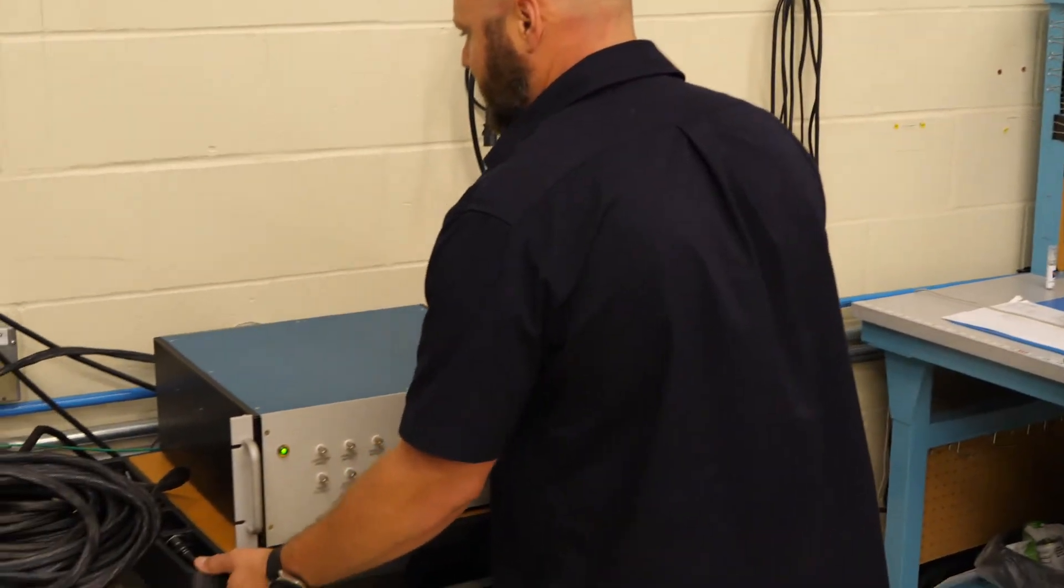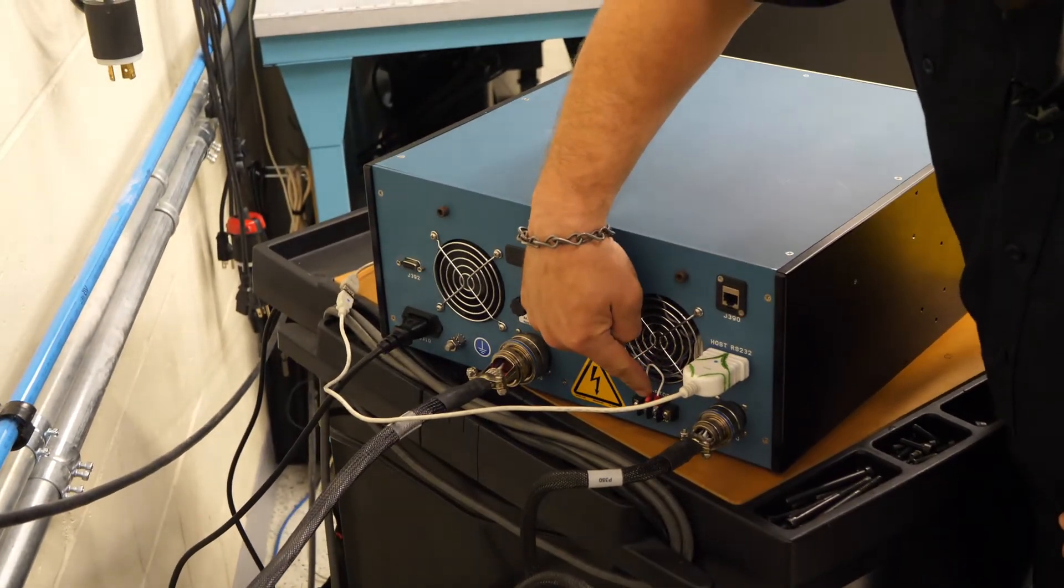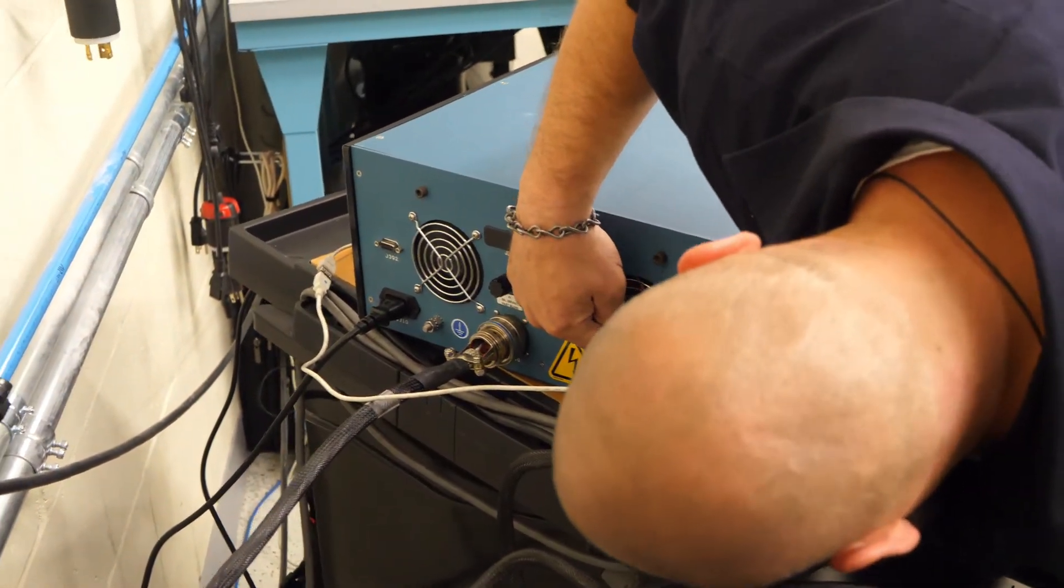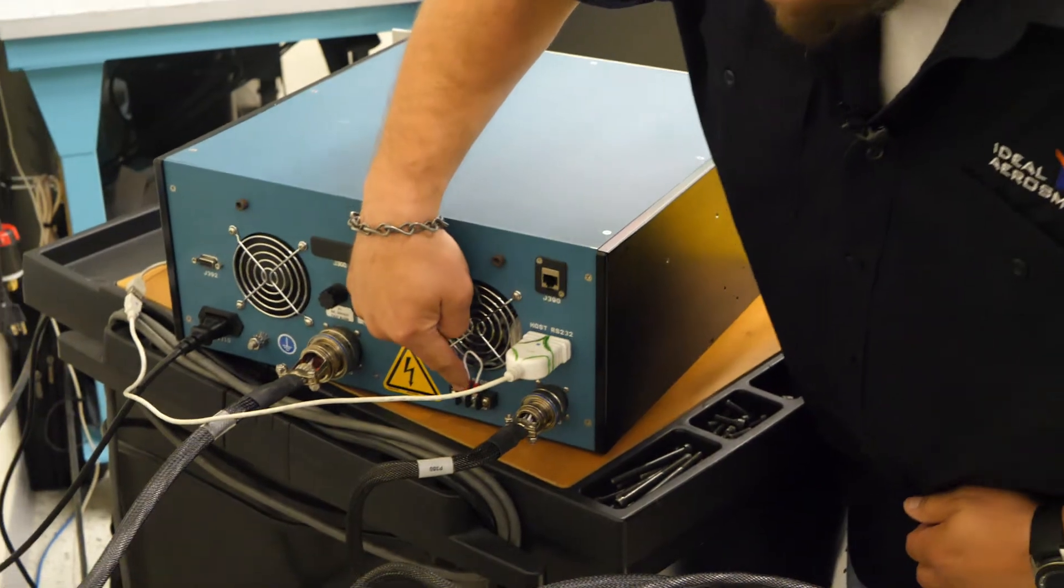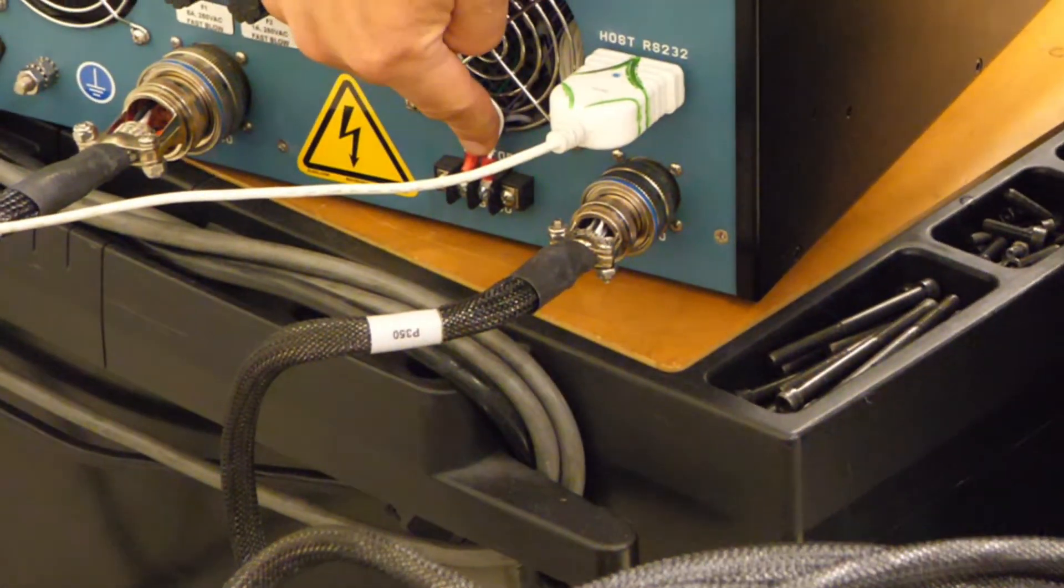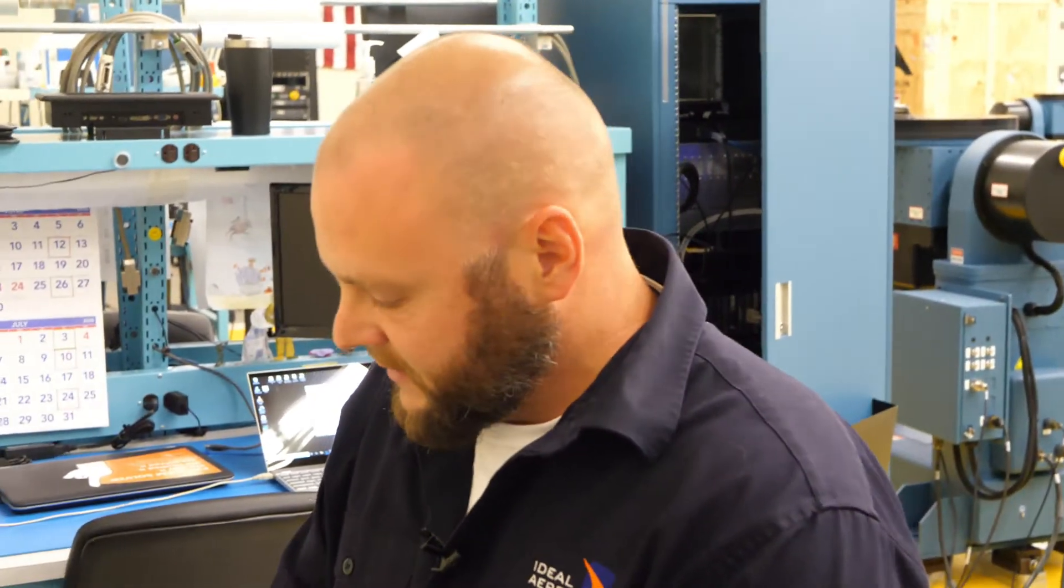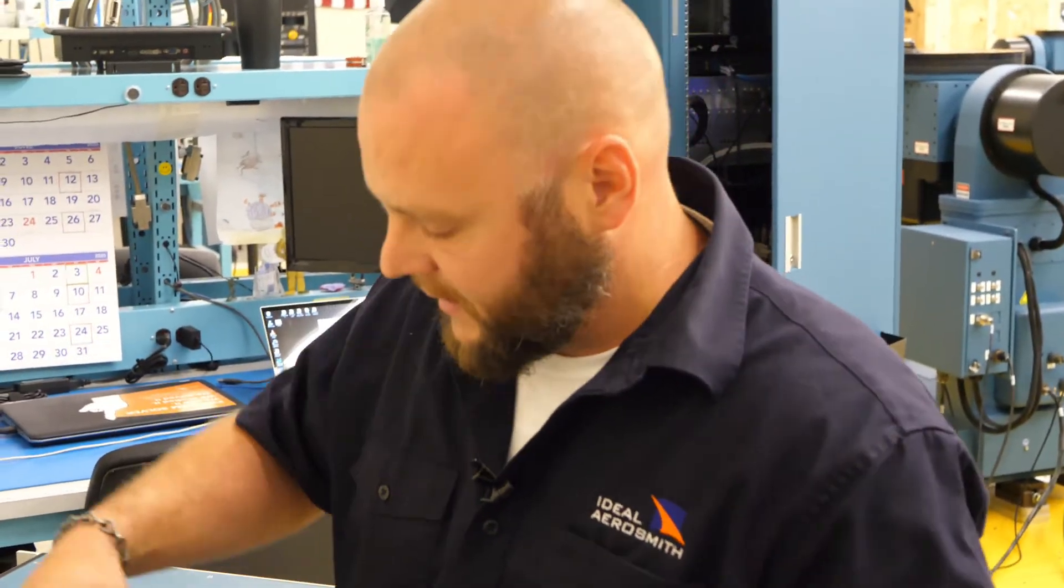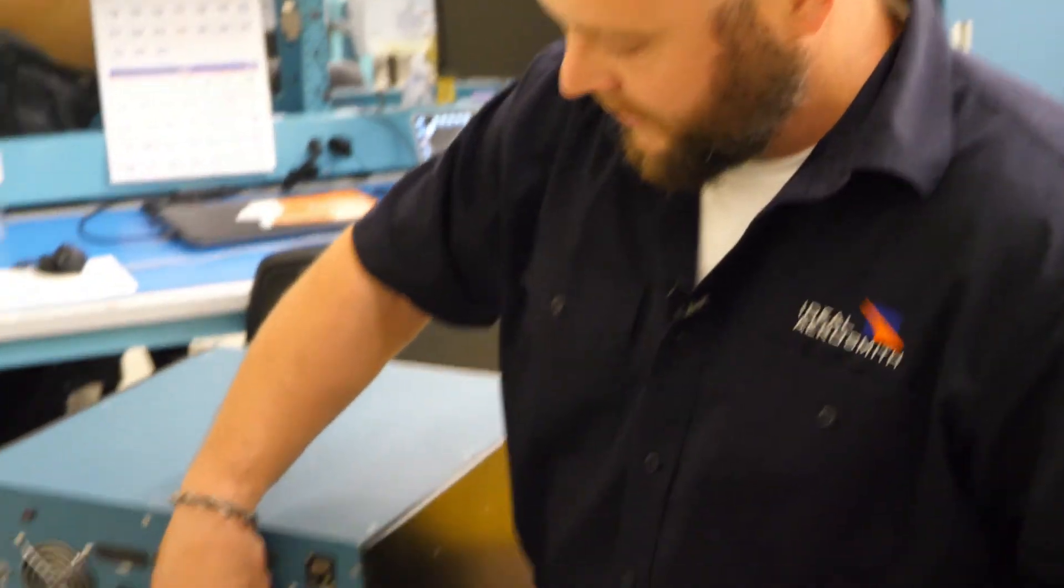On the back of the rate table, we will also want to make sure that the jumper is in place on the terminal block across the two middle, which is another part of the emergency stop loop, which you have access to if you desire to put your table in a safety enclosure or have some sort of interlock that will trip and not allow the rate table to run if someone's near it or whatever you plan on using.